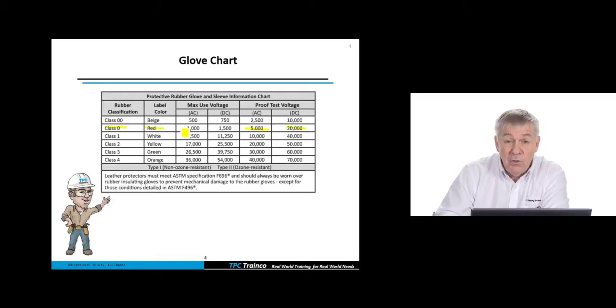Way above my use of that glove. I can use this glove all the way up to 1,000 volts AC and 1,500 volts DC. Do we have any questions at this moment in time? Just type them into your chat box if we do.